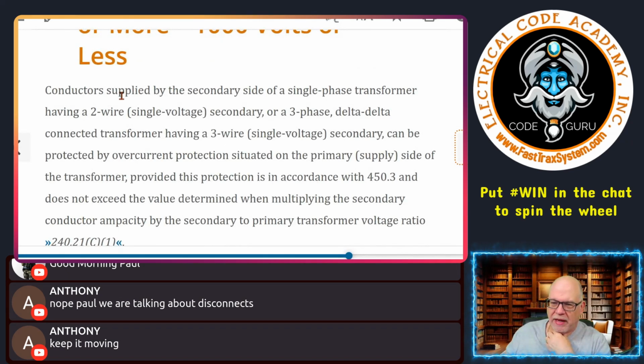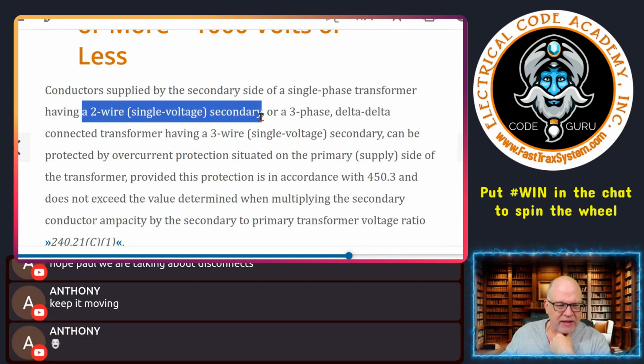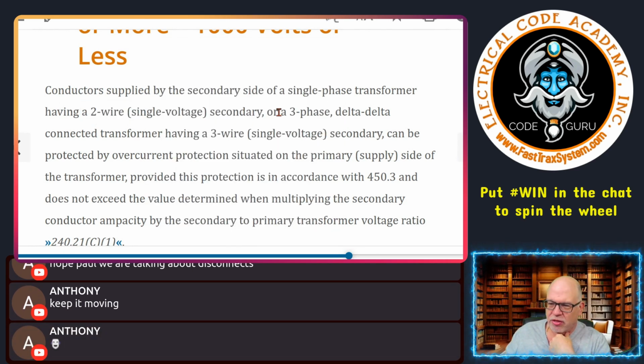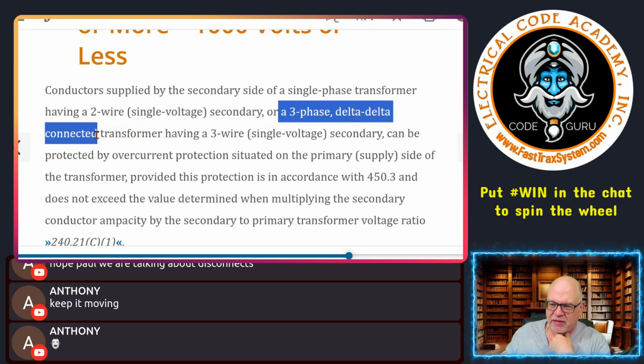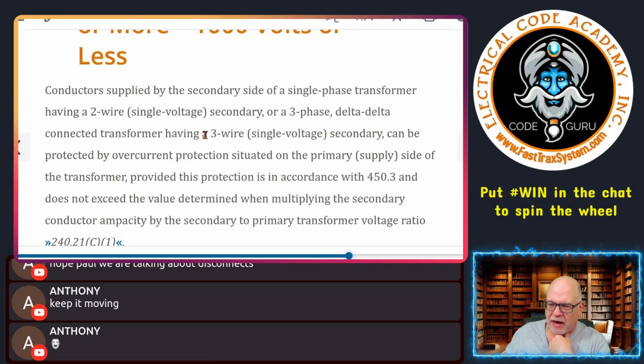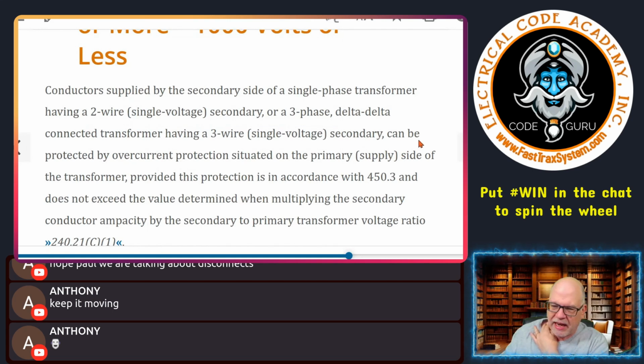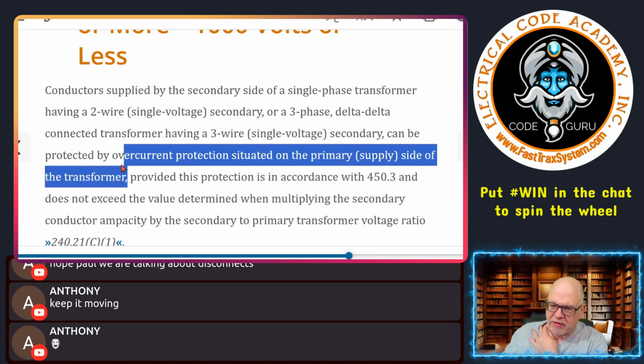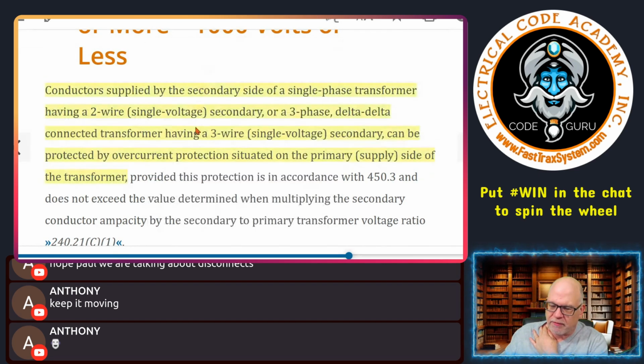So conductors supplied by the secondary side of a single-phase transformer having a 2-wire secondary, or a 3-phase delta-delta connection transformer having a 3-wire secondary, and both of these are single voltage, can be protected by the overcurrent protection situated on the primary side of the transformer. Let me explain this part real quick for those that are confused by that.